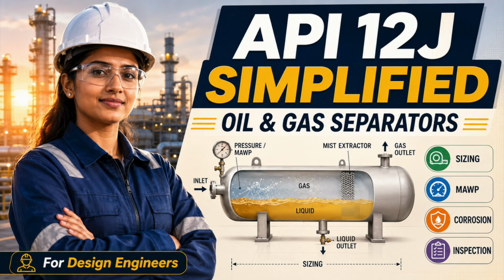If high liquid level can damage a compressor, contaminate downstream treatment, or create pipeline liquid accumulation, then the protection philosophy must be explicit. If low liquid level can send gas into a lower pressure liquid system, the downstream equipment must be protected. A separator is not merely controlled equipment.